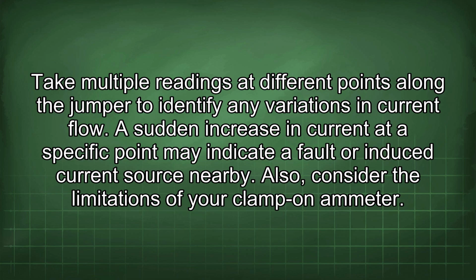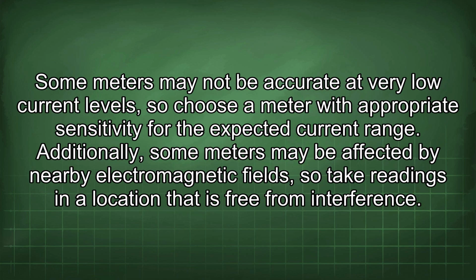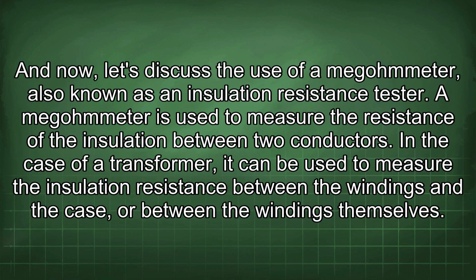Also, consider the limitations of your clamp-on ammeter. Some meters may not be accurate at very low current levels, so choose a meter with appropriate sensitivity for the expected current range. Additionally, some meters may be affected by nearby electromagnetic fields, so take readings in a location that is free from interference. And now, let's discuss the use of a megohmmeter, also known as an insulation resistance tester.